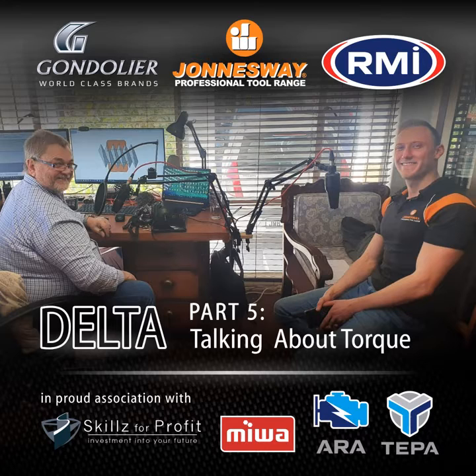For interest's sake, do you guys at Jonnesway in South Africa do torque wrench calibration on site, or is it a case where one sends the torque wrench into you to be done? No, you will have to send it into our service center. So what we basically have is a calibration tool, and it's actually quite big, so you wouldn't be able to do it on site. There is a big difference with Jonnesway calibrations: we actually do it in-house, which is great.